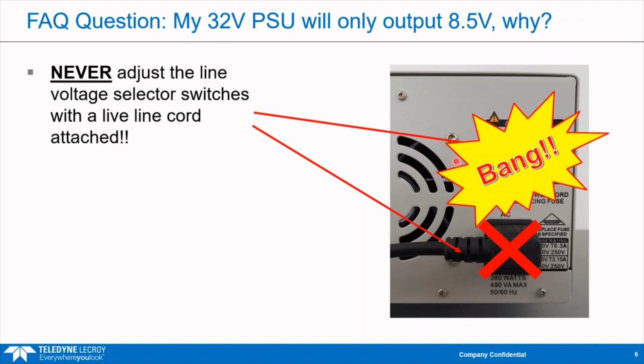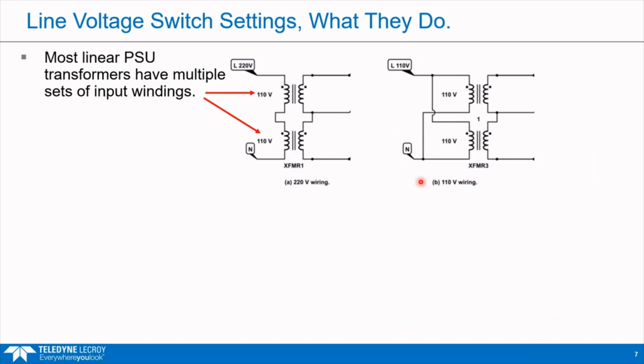I'm going to go through those switches in more detail. Most linear power supply transformers have multiple sets of input windings, as I showed on my small toroid. It has two sets of windings, each 110 volt, which are either connected in series, giving 220 volts input, or in parallel, giving 110 volts. I can see the wiring here connects these two in parallel for 110 volts.